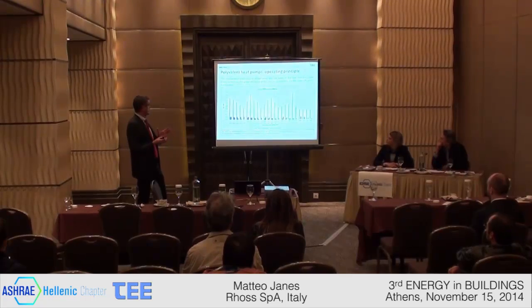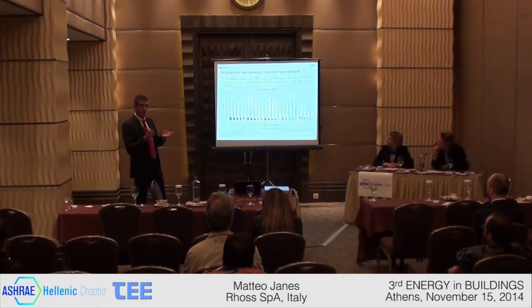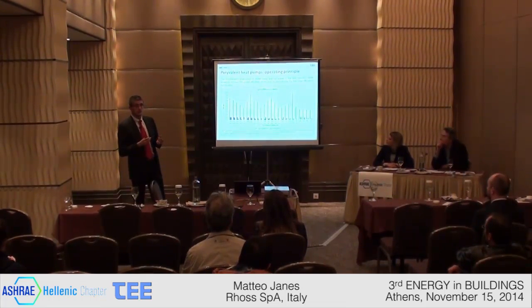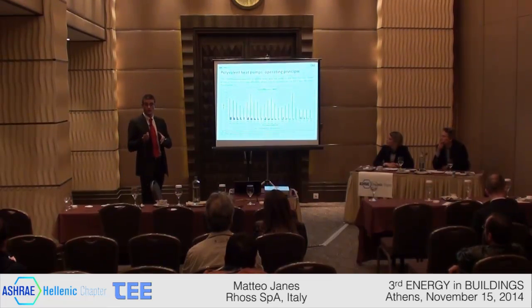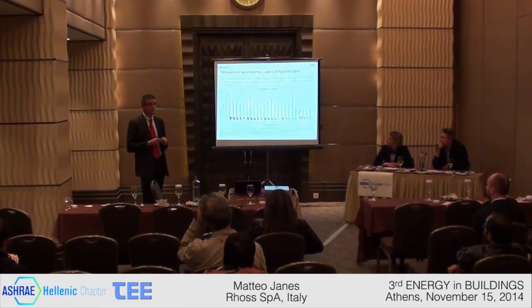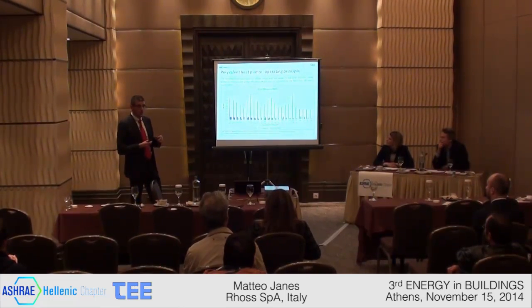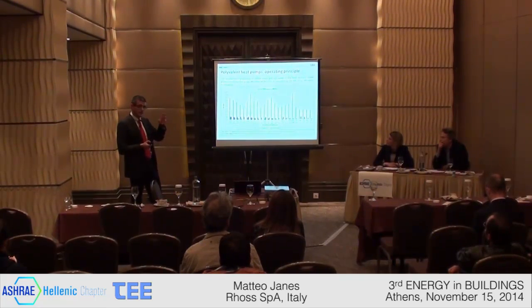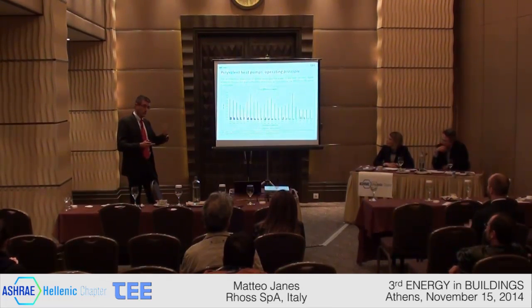The simultaneous production of chilled water and hot water in the total heat recovery mode allows us to increase the global efficiency of the unit. Maybe you are familiar with the concept of EER, energy efficiency ratio, for a chiller, which is the ratio between the cooling capacity and the power input used to obtain this cooling capacity, or the COP for a heat pump, which is the ratio between the heating capacity and the power input used. In this case, we have the simultaneous production of cooling capacity and heating capacity.